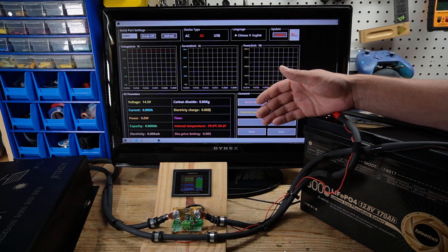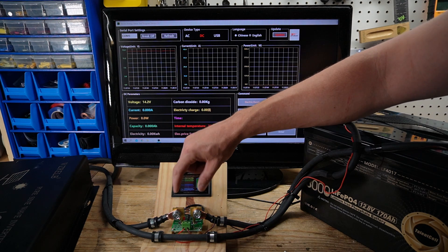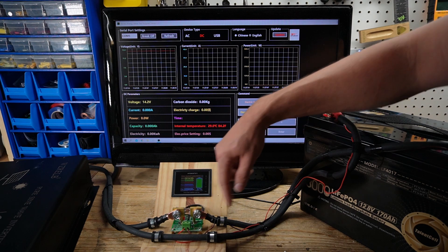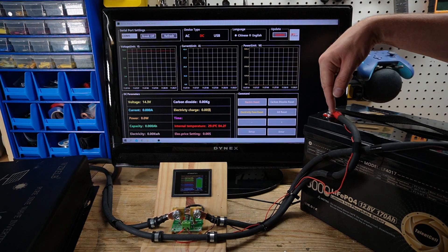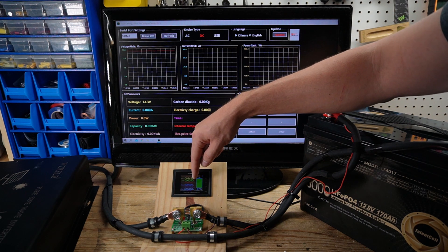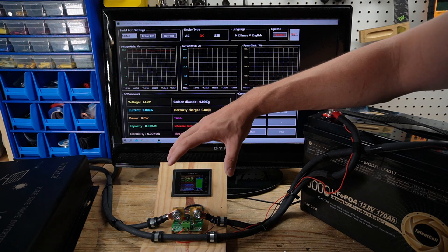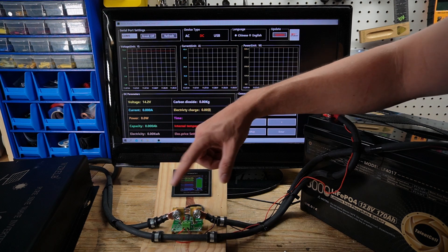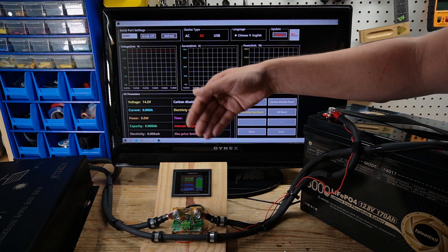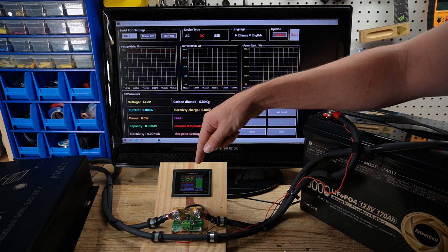So now it's time to start the discharge test. This is the same setup I use on all my batteries. I have the torch tester with the torch shunt, and I have my voltage positive and negative sample cables running directly to the lugs connected to the battery. The negative runs through the shunt, gives me a reading on this screen, which also gives me a reading on this screen via Bluetooth. This setup only works in one direction. If you want to use this as a setup for monitoring in your RV or trailer, I wouldn't suggest it because you will not get a charging and discharging sample.